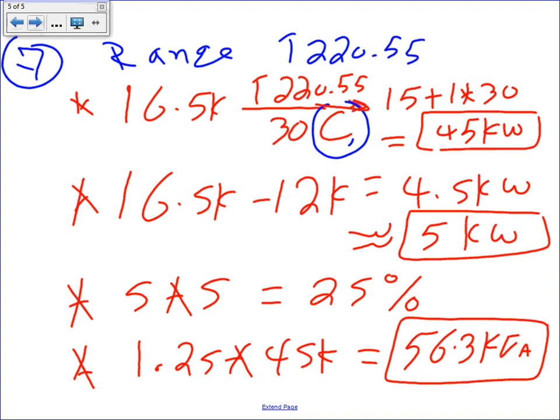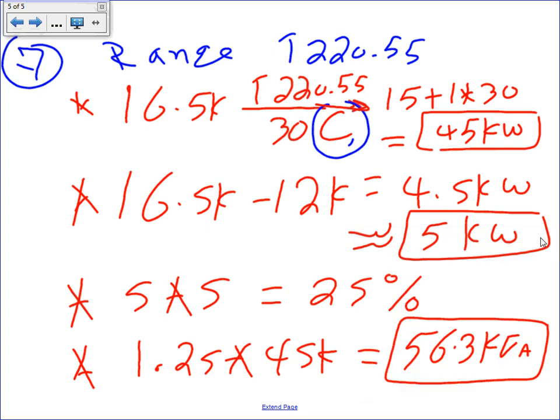Any questions? Can I repeat this one more time? You take the 16 kW under column C for 30 of them, and you have to calculate the demand for 30 of them. That will get you 15 from the get-go plus 1 kW for every range. That gives you 1 times 30 plus 15, 45. It's not enough. Had this number been 12, we're done. But unfortunately, it's not 12.